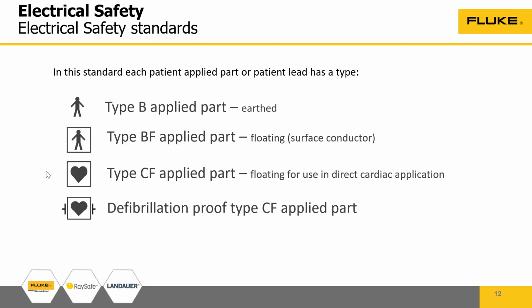Why is it classified? Type B, BF, CF. Again, as I said, the IEC recommendation changes based on the type of equipment. So it is very important to understand what kind of medical device you are testing, and based on that, follow the proper guidelines.